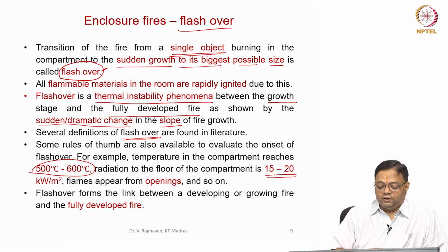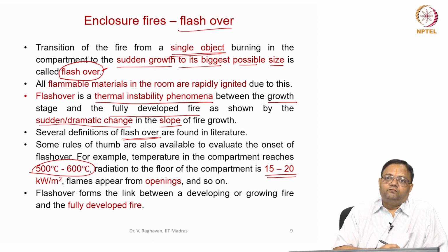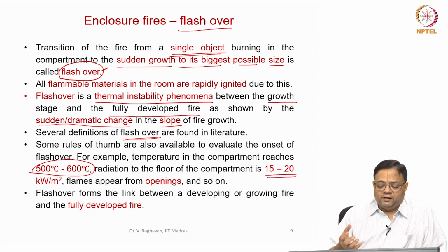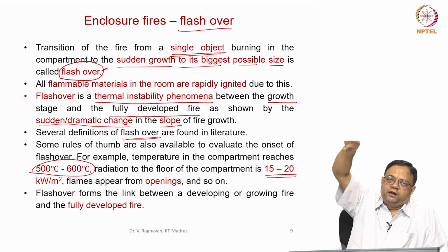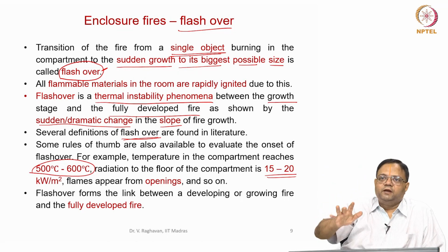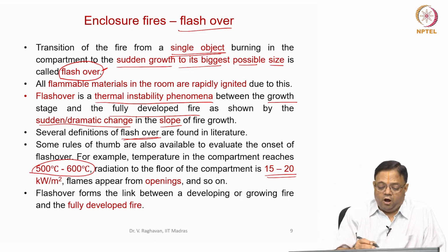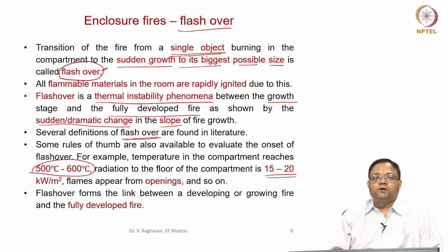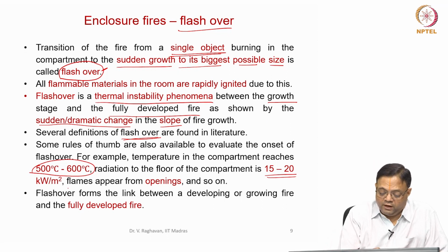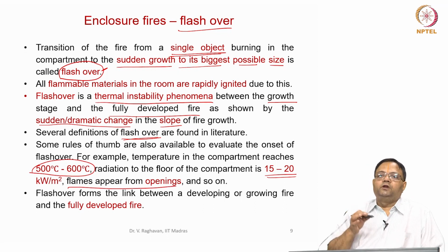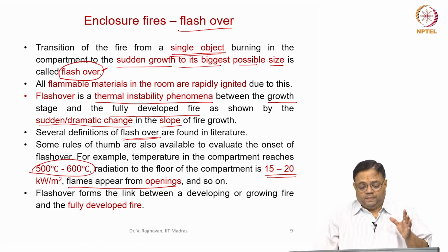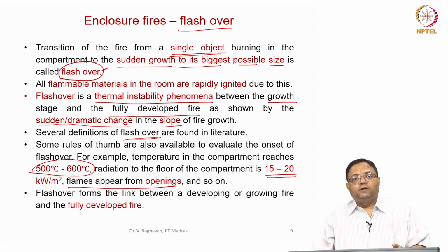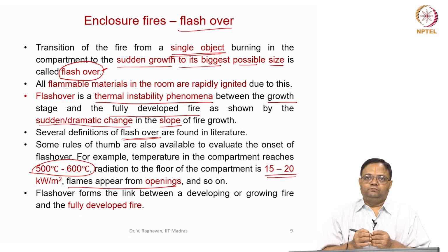Now, what happens is the flashover will occur, we can say. There are several things. We can say that the sudden heat release rate increase or temperature increase can be the indication for this flashover, or the compartment temperature itself reaching about 600 degrees plus is an indication of flashover, or if you see flames coming out of the opening, that is also an indication of flashover, etc.